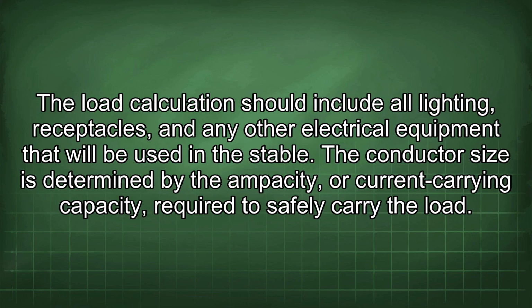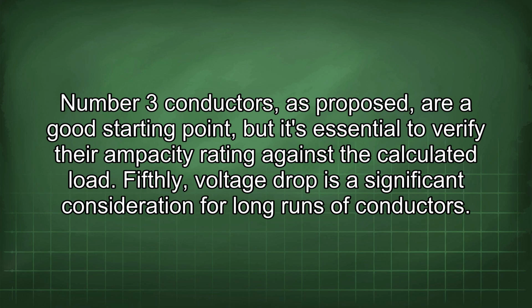The load calculation should include all lighting, receptacles, and any other electrical equipment that will be used in the stable. The conductor size is determined by the ampacity, or current carrying capacity, required to safely carry the load. Number 3 conductors, as proposed, are a good starting point, but it's essential to verify their ampacity rating against the calculated load. Fifthly, voltage drop is a significant consideration for long runs of conductors.